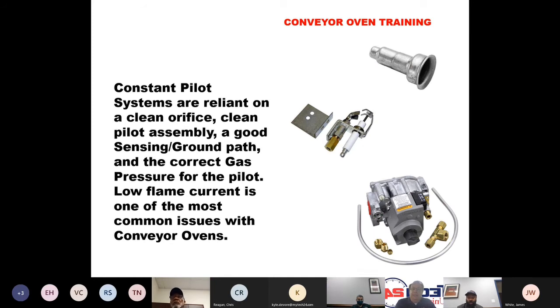So these constant pilot systems are reliant on clean orifices, clean pilot assemblies, and a good ground sensing path. You must have the correct gas pressure for the pilot. Low flame current, low gas pressure, a clogged orifice, or a dirty pilot are the most common issues in conveyor ovens. So these are just some basic things to make sure you're checking when you're looking at ignition problems.